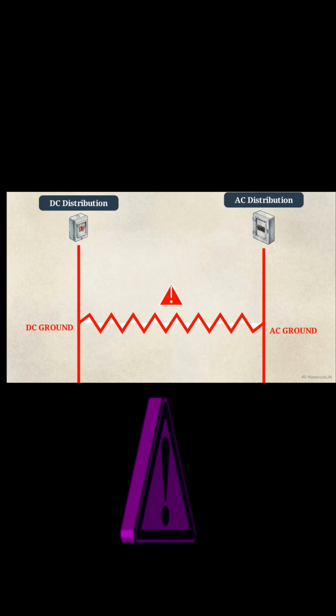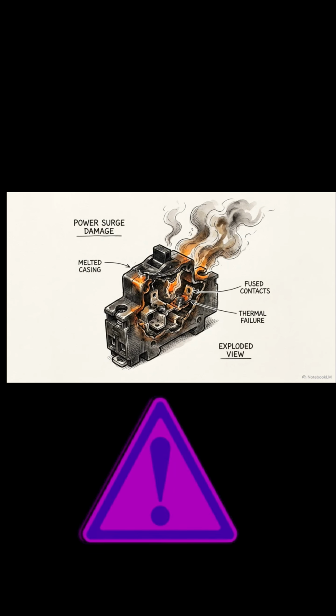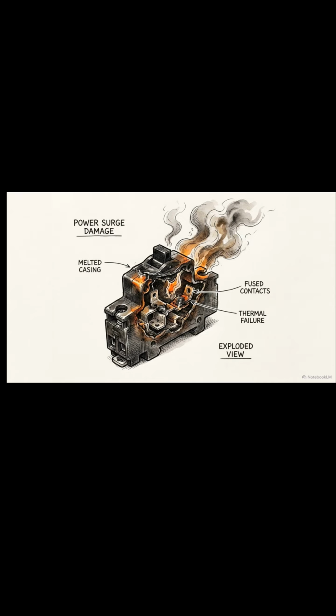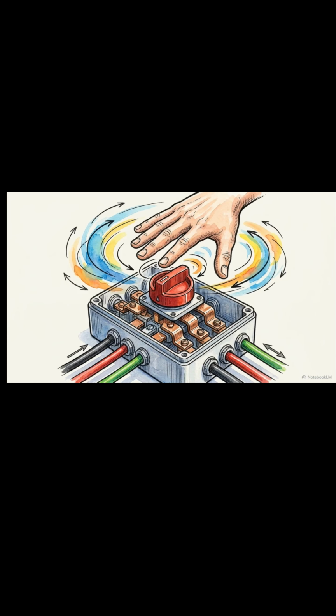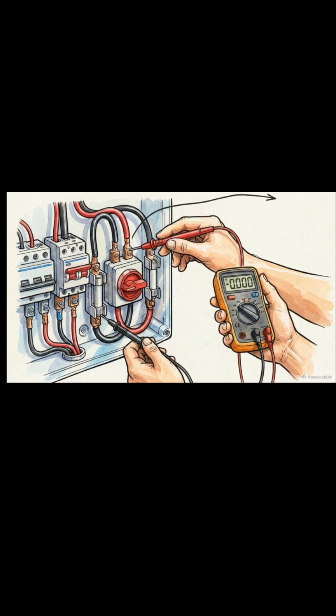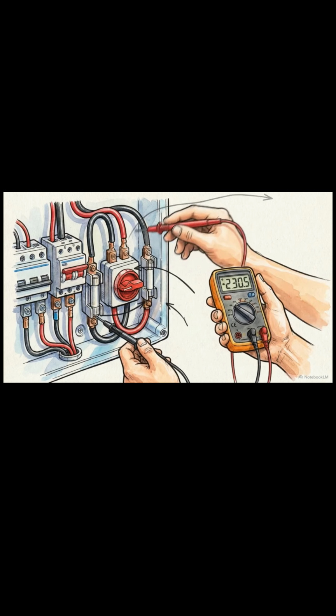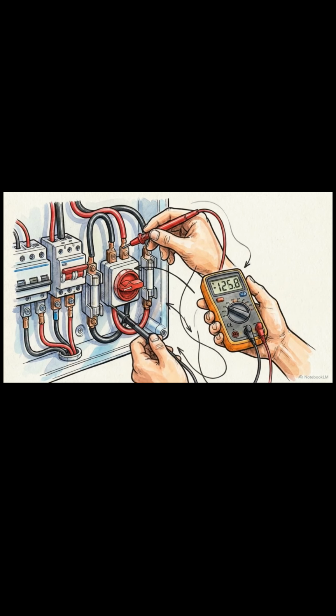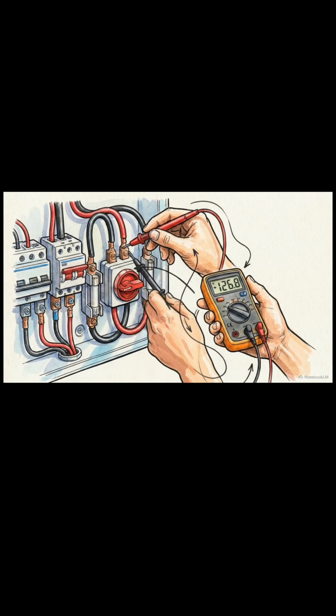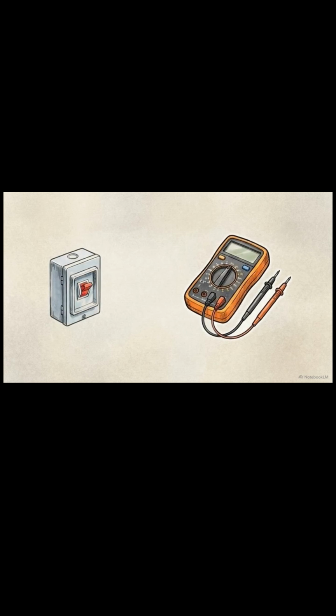Mixing your DC and AC grounds creates a dangerous electrical loop that bypasses your breakers, rendering the entire safety architecture of your installation useless. The wiring is in place, but we don't flip the switches yet. We first have to verify the open circuit voltage, the maximum voltage the modules produce when disconnected, and confirm the electrical polarity is correct. This graphic illustrates the testing procedure.